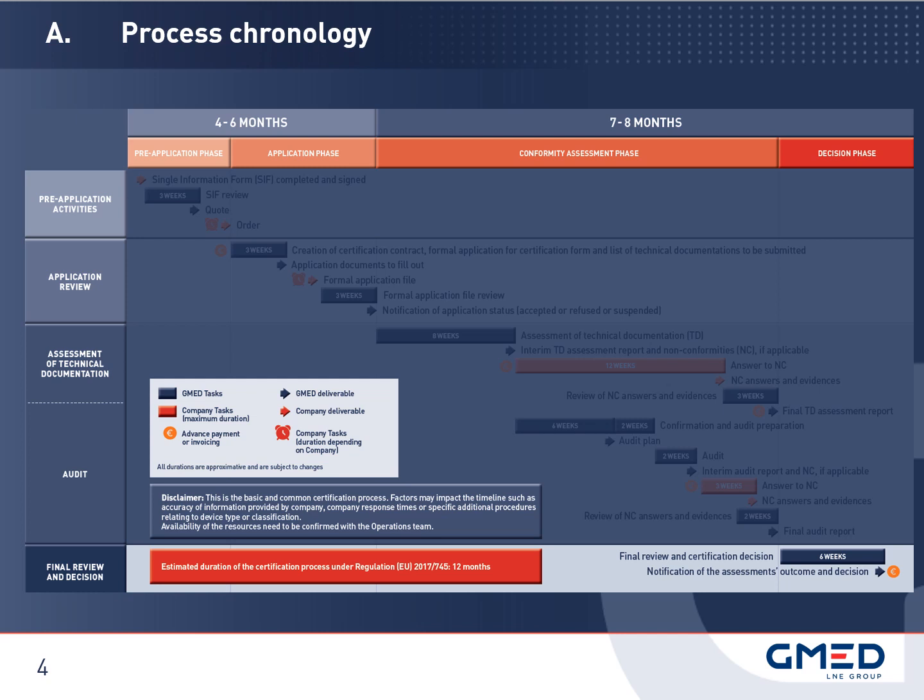This phase does not correspond to a simple conclusion or closing stage of the conformity assessment activities carried out, but rather to a milestone prior to the issue of the certificate, during which the notified body will ensure that all conditions are met to be able to pronounce in favour of certification under Regulation EU 2017/745.